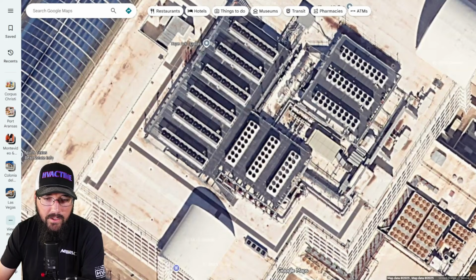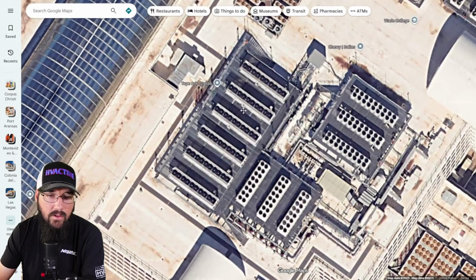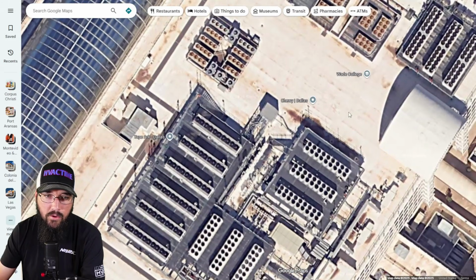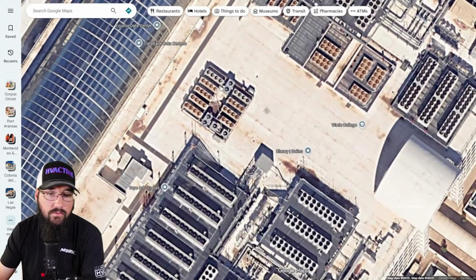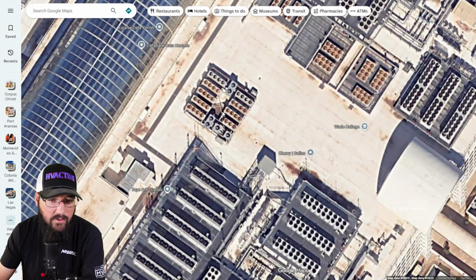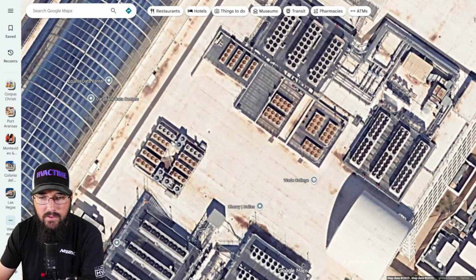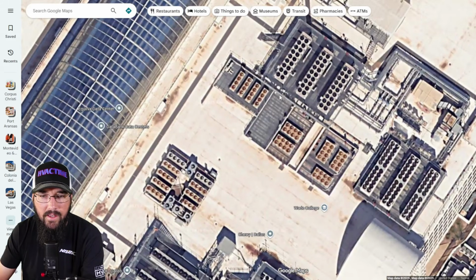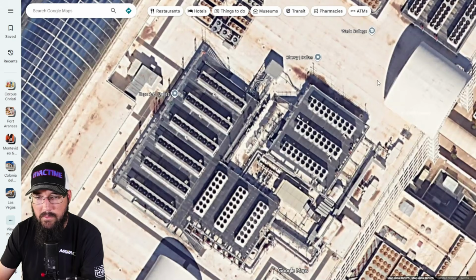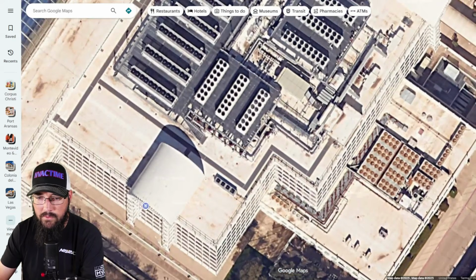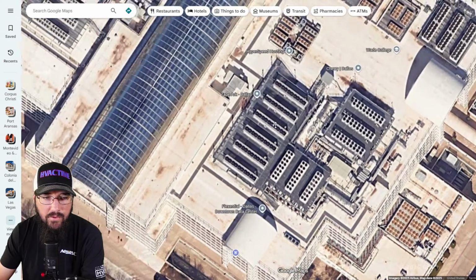You'll see that the entire top deck of the chiller is just a condenser fan deck all the way across. Now you have to be careful because there could be some large refrigeration racks that look very similar. I'd argue that these over here, with single line fan decks, could just be a set of refrigeration racks for some rack units. But these are air-cooled chillers - these are your chilled water pipings coming in and out. That's what this whole setup is, sitting up on some pedestals on the roof. That's what these are over here, these all look like air-cooled chillers. So this is what you're looking for.